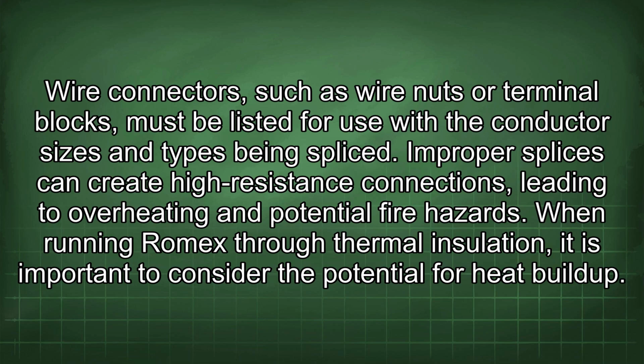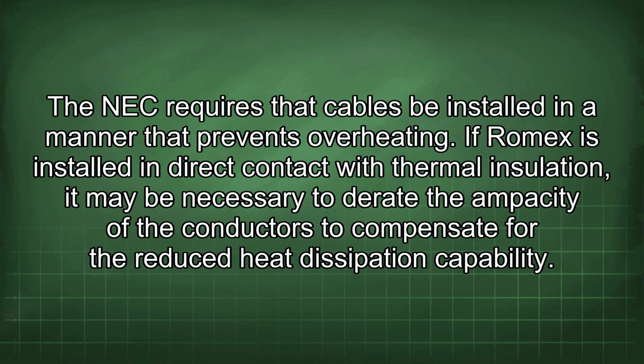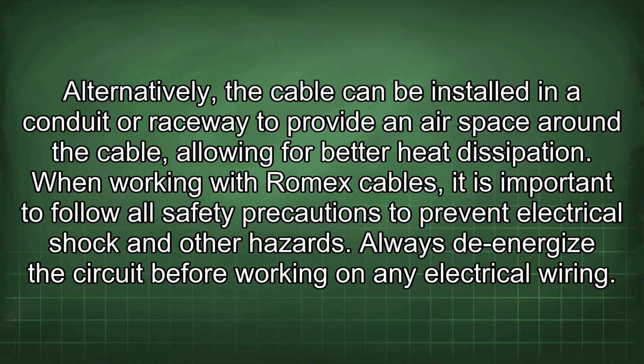When running Romex through thermal insulation, it is important to consider the potential for heat buildup. The NEC requires that cables be installed in a manner that prevents overheating. If Romex is installed in direct contact with thermal insulation, it may be necessary to derate the ampacity of the conductors to compensate for the reduced heat dissipation capability. Alternatively, the cable can be installed in a conduit or raceway to provide an airspace around the cable, allowing for better heat dissipation.